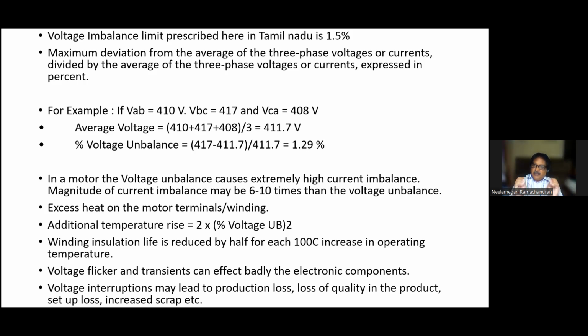It is very easy: you just connect it to the fuse and take a temporary connection. So in one phase, all the single phase equipment will be loaded. So when the motor on that DB is running, we get this problem. So these kinds of problems can be avoided. This is on the voltage side.